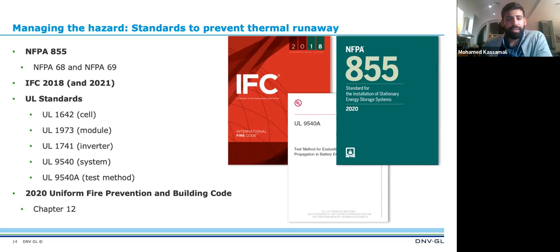Off of NFPA 855, you'll see that IFC 2021, the fire code within New York City, and the California fire code have adopted NFPA 855 to certain degrees. There might be exceptions or variations in certain instances, but for the most part they're very well aligned. NFPA 855 was the culmination of a lot of these codes being improved to fit the needs of energy storage safety. Within NFPA 855, it prescribes NFPA 68 and NFPA 69 as mechanisms for examining, calculating, and designing explosion protections, which NFPA 855 calls out as required for all lithium ion technology. That may vary by code, but in New York City that's accounted for, and certainly should be.